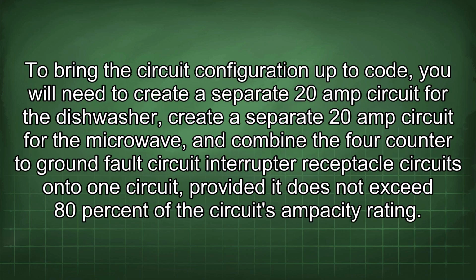To bring the circuit configuration up to code, you will need to create a separate 20-amp circuit for the dishwasher, create a separate 20-amp circuit for the microwave, and combine the 4 counter ground fault circuit interrupter receptacle circuits onto one circuit, provided it does not exceed 80% of the circuit's ampacity rating.